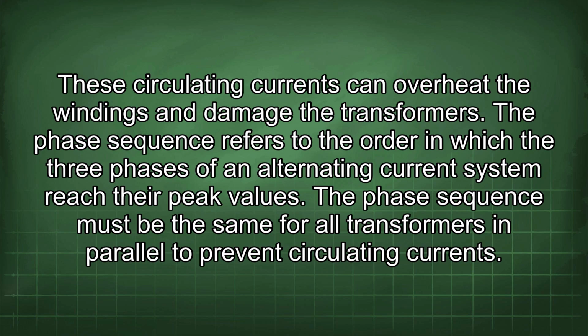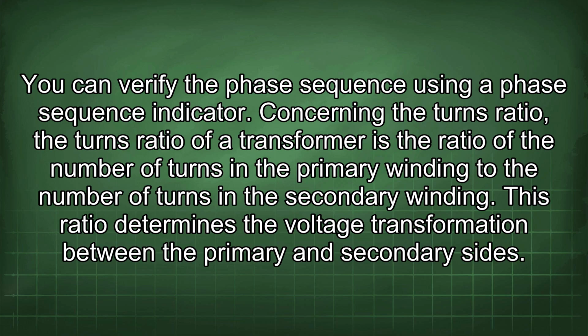The phase sequence refers to the order in which the three phases of an alternating current system reach their peak values. The phase sequence must be the same for all transformers in parallel to prevent circulating currents. You can verify the phase sequence using a phase sequence indicator. Concerning the turns ratio, the turns ratio of a transformer is the ratio of the number of turns in the primary winding to the number of turns in the secondary winding. This ratio determines the voltage transformation between the primary and secondary sides.